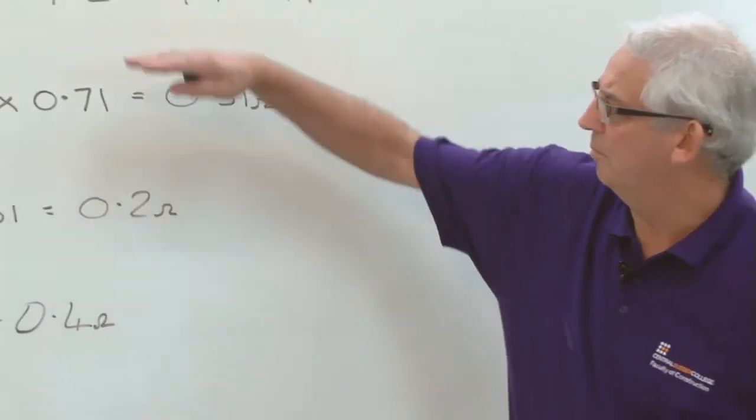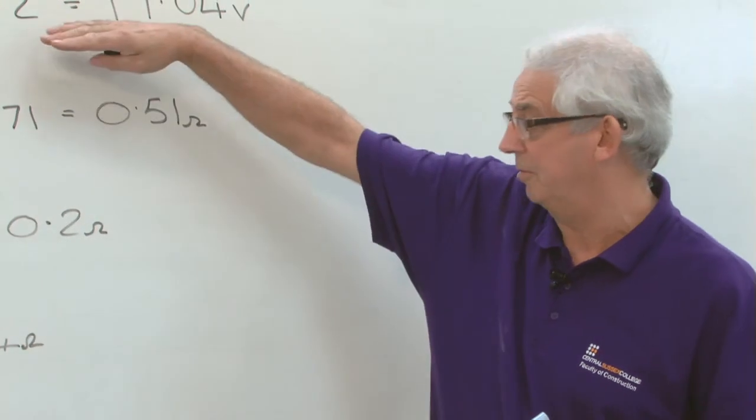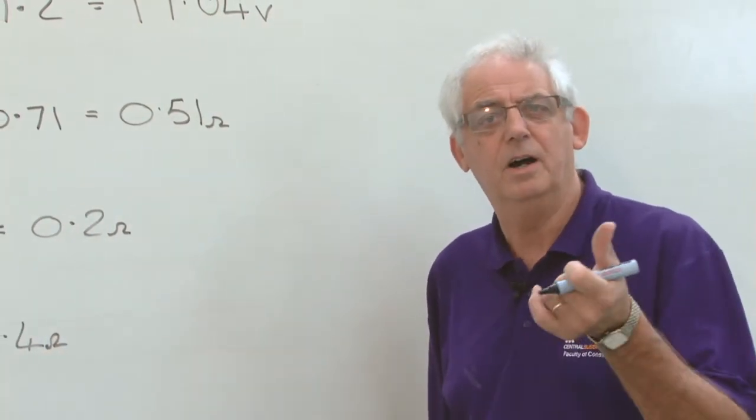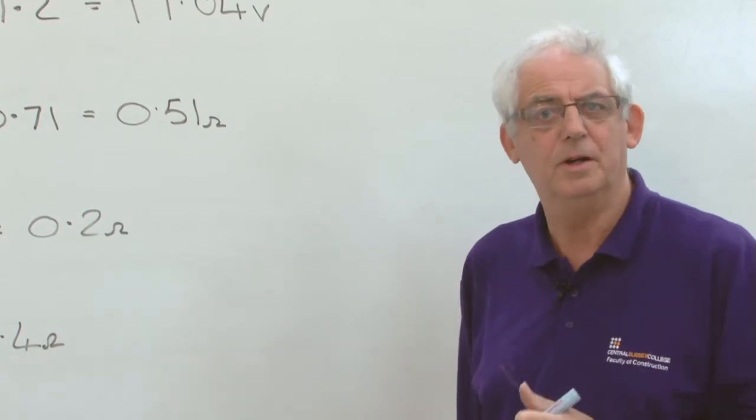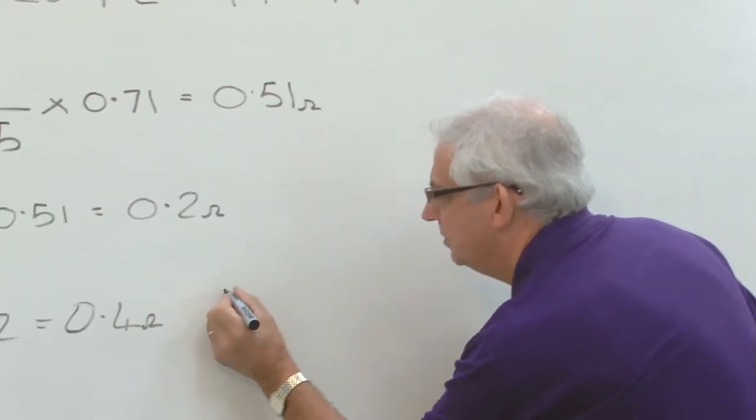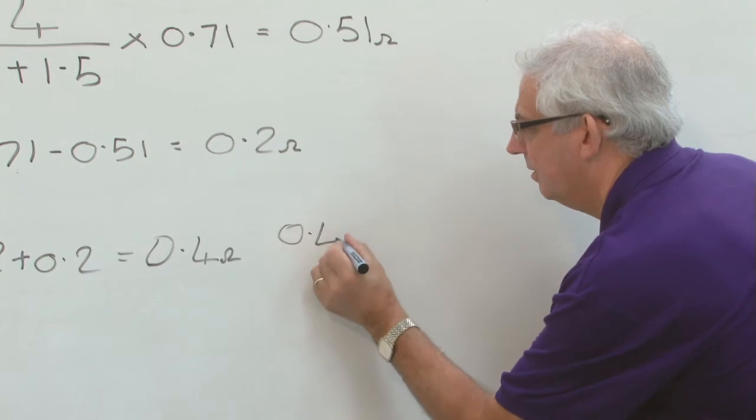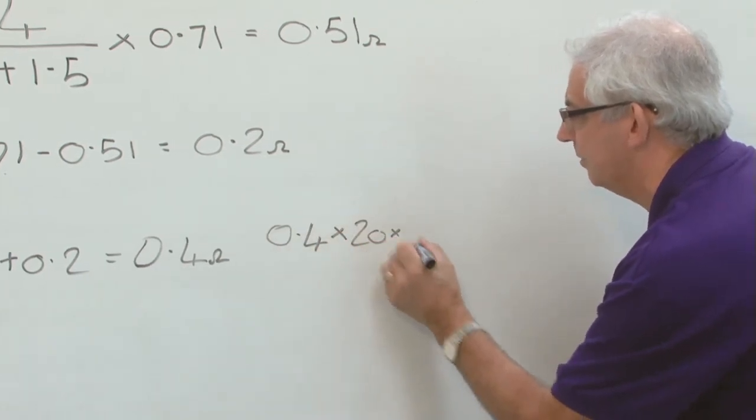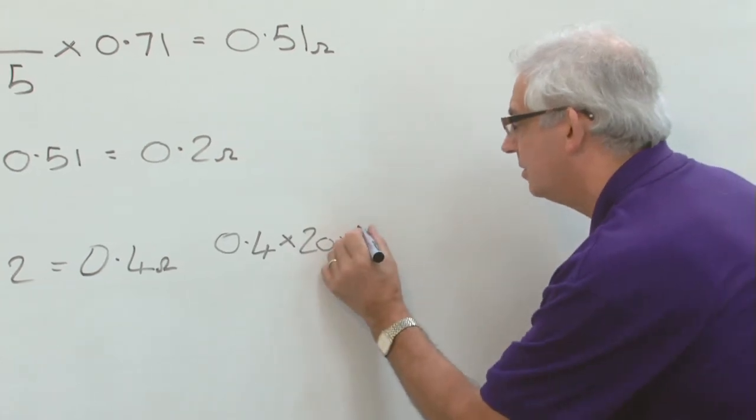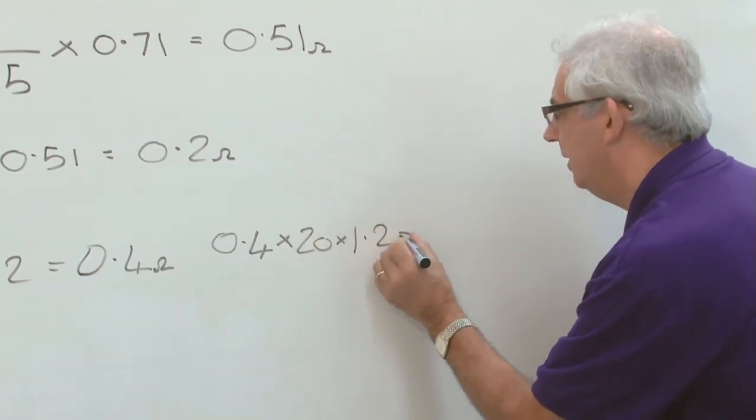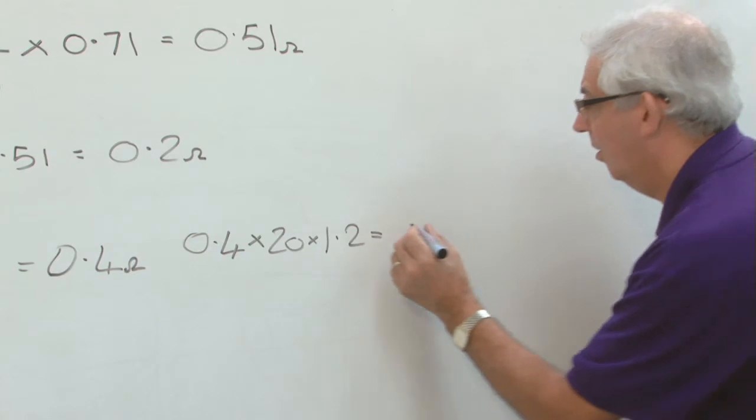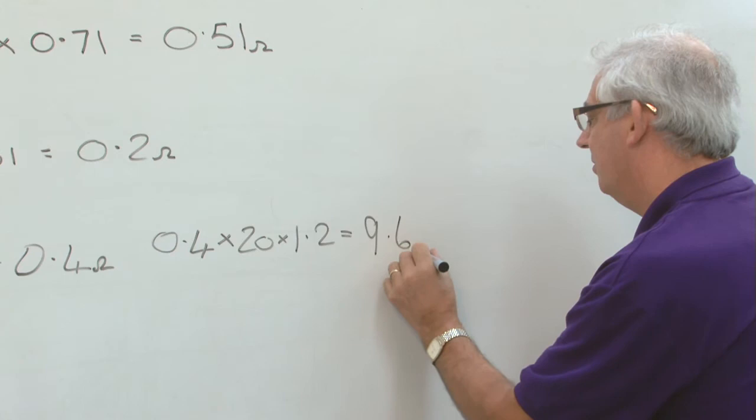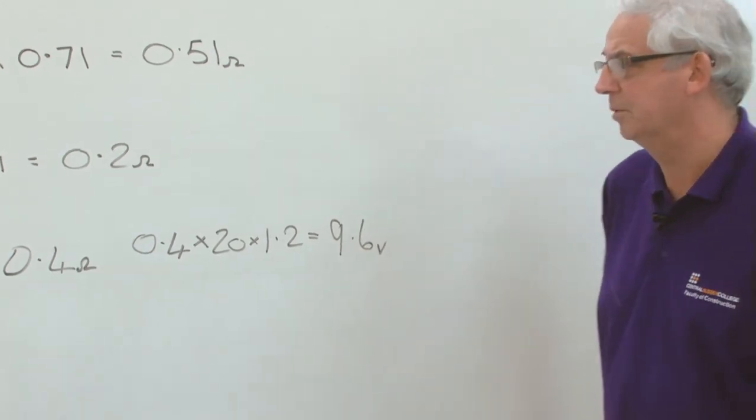Now I can revert back to my old calculation, on my first calculation using 0.4 because I've now got Rn plus R1. 0.4 times 20, the rating of the protective device, times 1.2 gives me a value of 9.6 volts, which is perfectly acceptable.